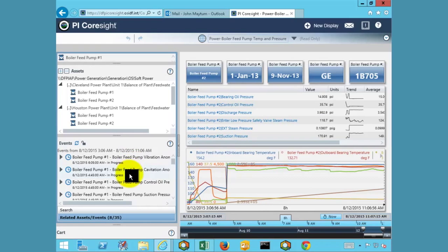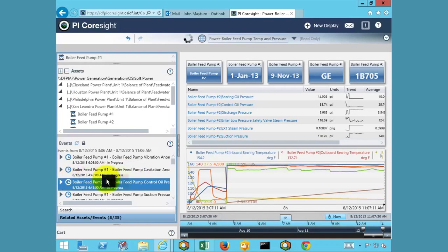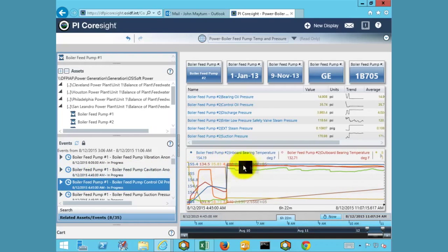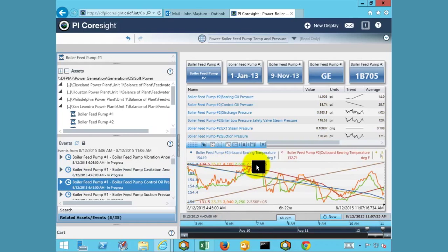Many are not tied to the bearing temperature violation that caused the notification. This indicates that the boiler feed pump could be suffering from chronic issues that need to, at a minimum, be addressed via visual inspection. In cases where we wish to view the data associated with a specific event, selecting on said event will set the time context of the display accordingly, allowing us to better visualize operating conditions during the pertinent excursion.